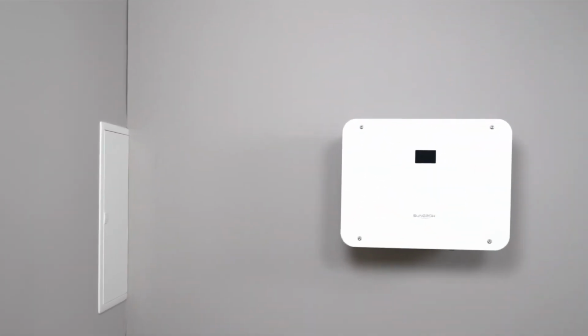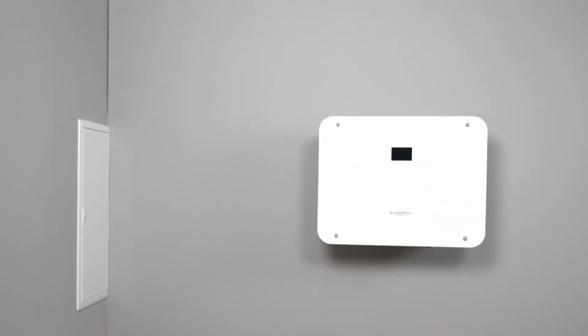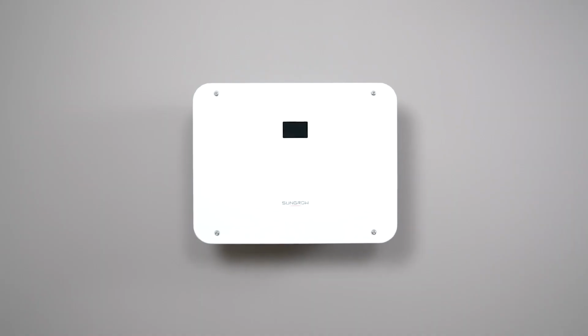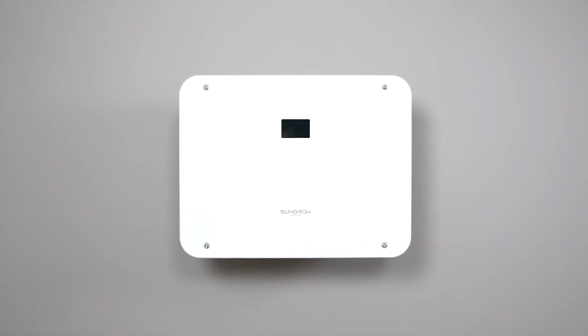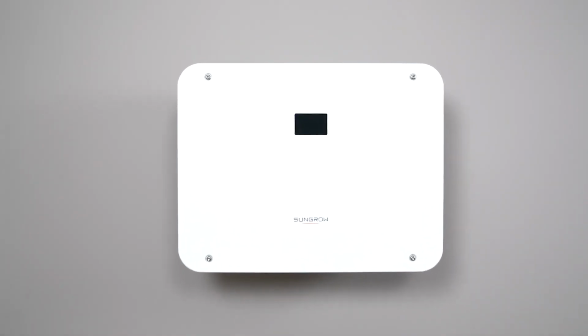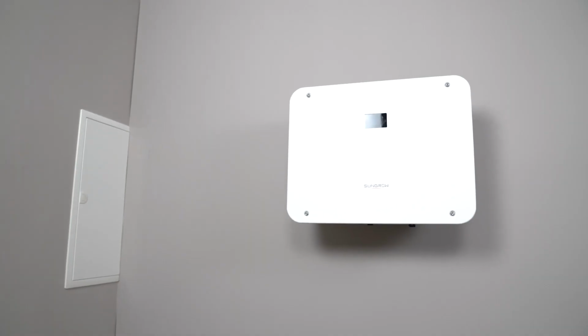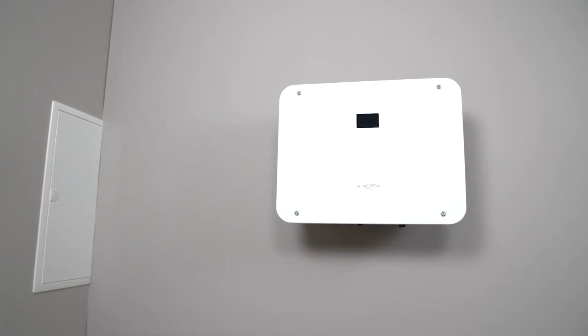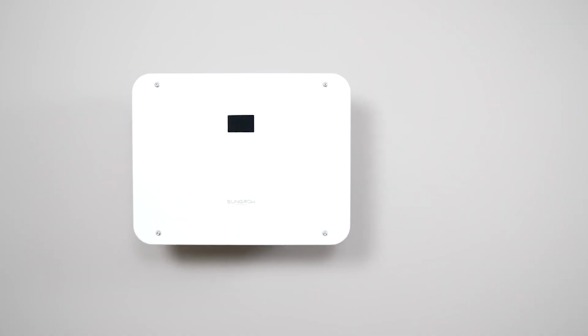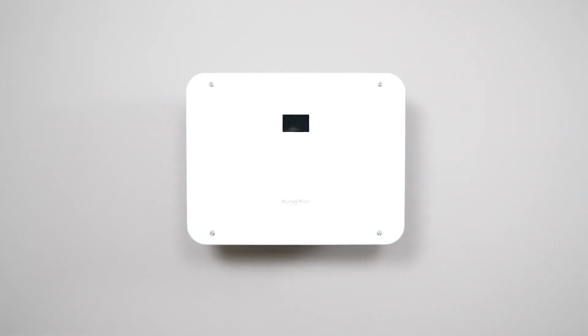You need a suitable place for the inverter. This means it should be a room where no flammable materials or gases are stored. Furthermore, the inverter should not be exposed to direct sunlight, rain or snow. Make sure to maintain the correct distances from the inverter and have sufficient space for the installation. Check the user manual for the right measurements.